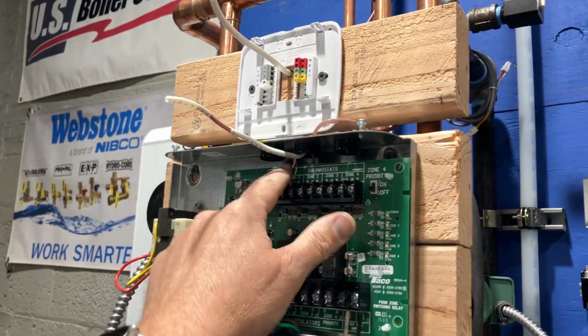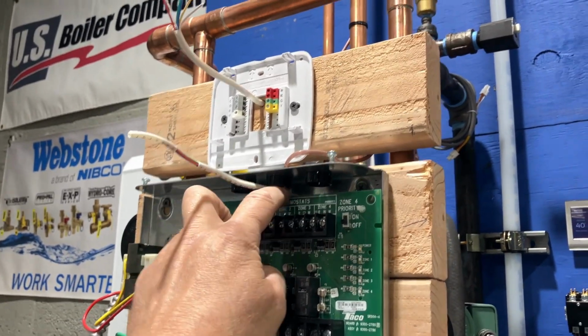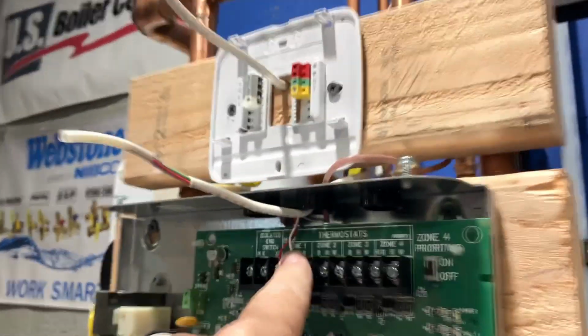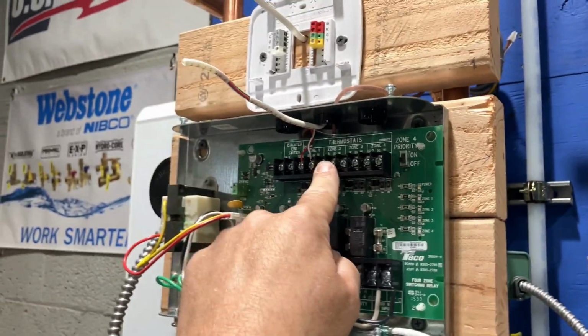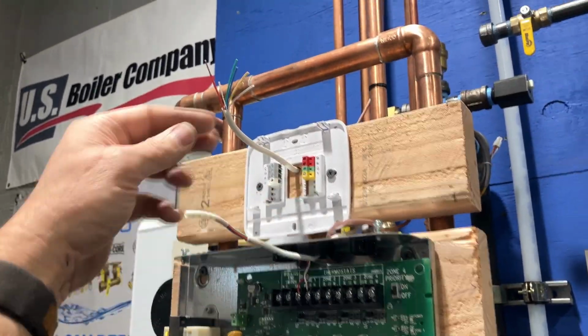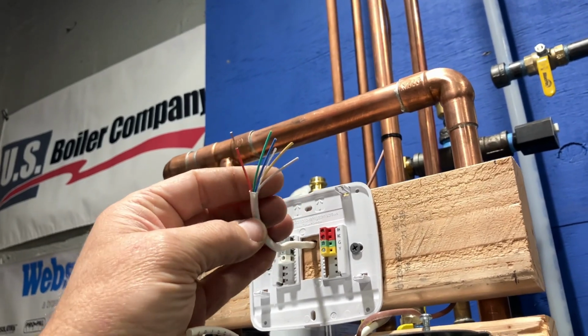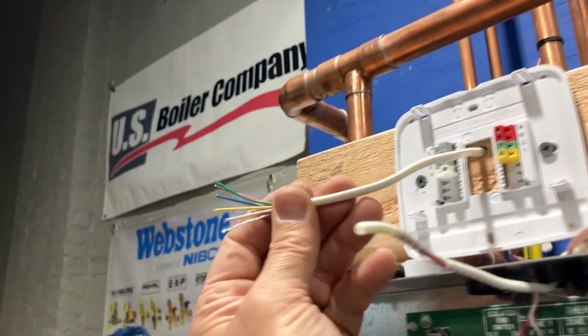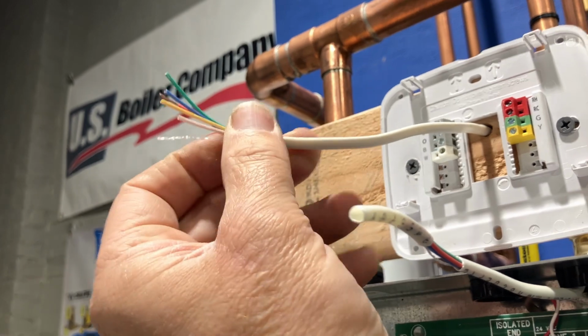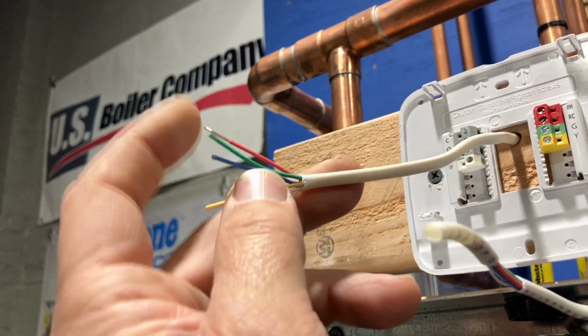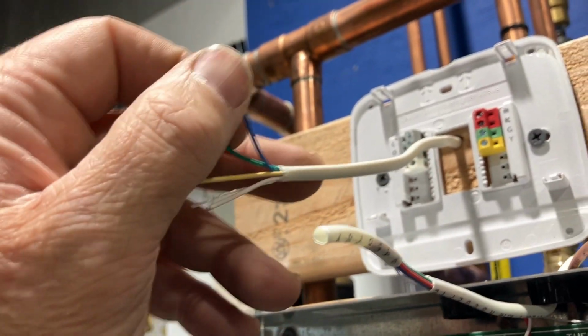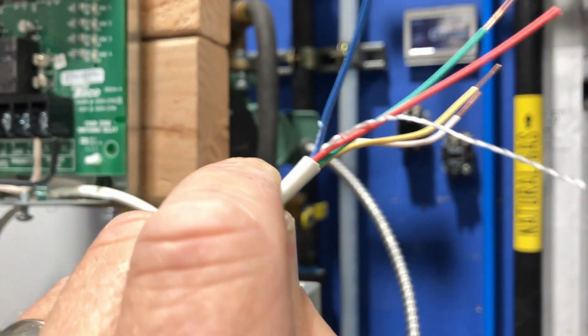Zone 1's already wired with R and W, the little string hanging out there. Just keeping it real. So we're going to wire in zone 2 from the thermostat here. Most of the wiring is already stripped there. Now, when you cut away the insulation around the conductors, you want to make sure you don't nick any of the insulation on the conductors, kind of like I did with that one right there. See, it's a little nick.